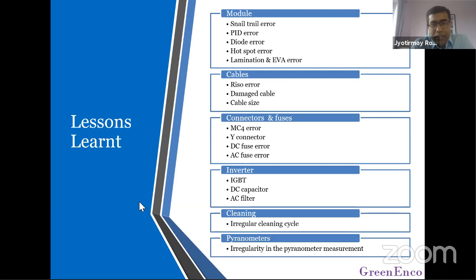Another example is the Y connector, which is quite common in India, where 2 4-square-mm cables come into the Y connector and go out as a 6-square-mm cable. Through diagnostics and data analytics, we identified that roughly 40 to 60% of some strings were underperforming compared to expected. Using a handheld thermal camera, we did IR inspection of those strings and could clearly see a temperature difference on one side of the Y. As soon as we replaced those Y connectors, generation immediately went back up to the expected level. These are just a few examples of what we've observed.